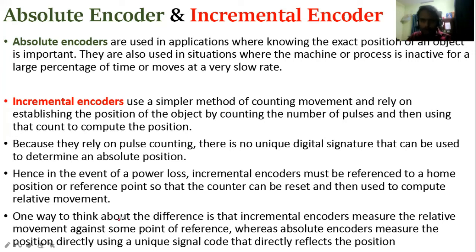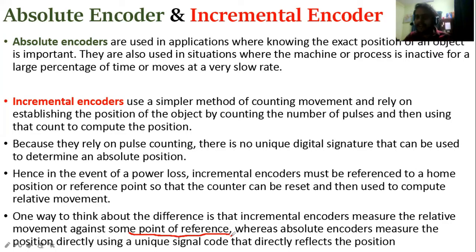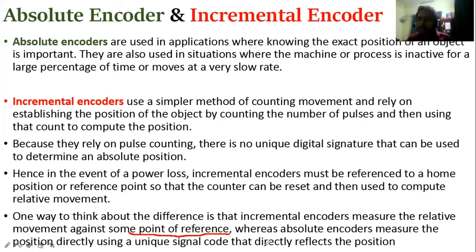One way to think about the difference: incremental encoders measure the relative movement against a reference point. Absolute encoders, in contrast, measure the position directly using a unique signal code — a binary code — that represents the position even after a power loss.